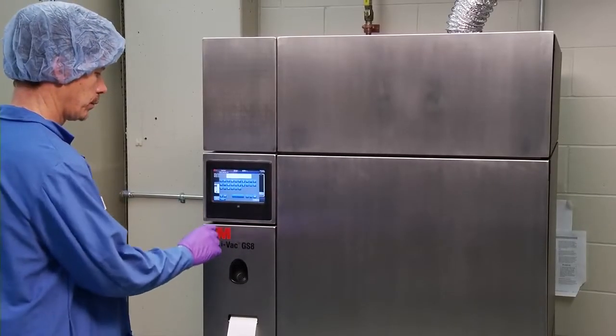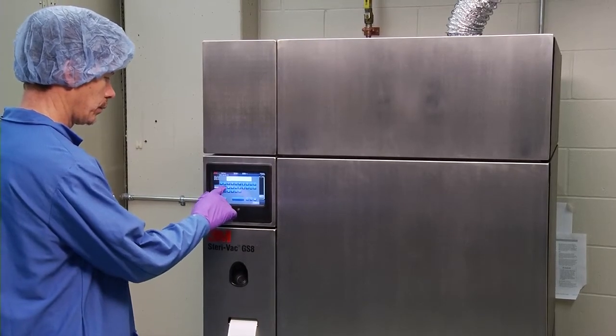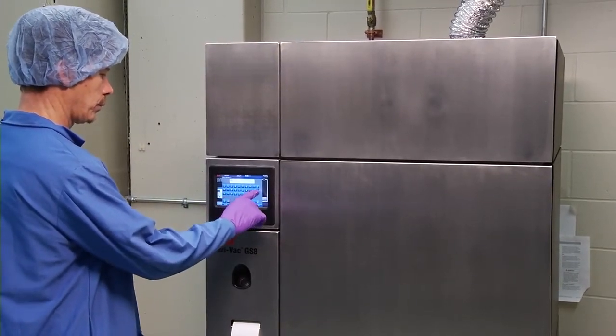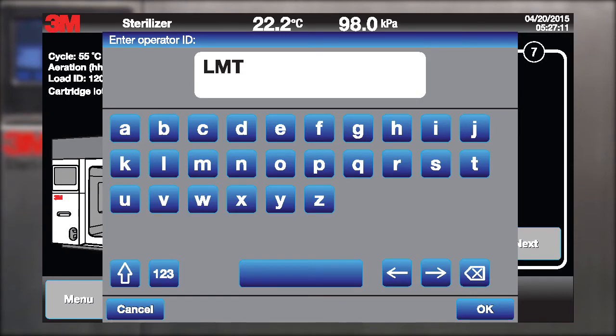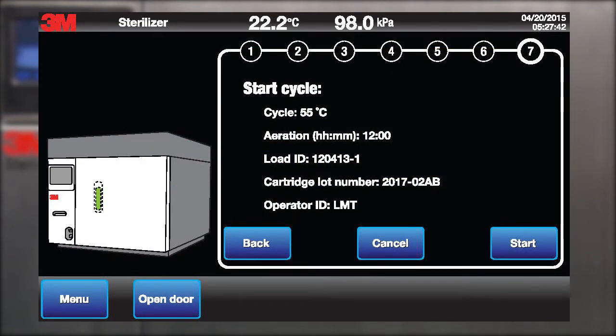Step 6 is an optional step where you can create an operator ID. Touch the screen in the operator ID field and an alphanumeric pad will appear. Enter an operator ID. Step 7. Review the program sterilization cycle. The options shown on the display screen are Back, Cancel the cycle, or Start the cycle. The screen also displays a green cartridge icon indicating that a full cartridge was placed into the sterilizer cartridge holder. Select Start to begin the cycle.